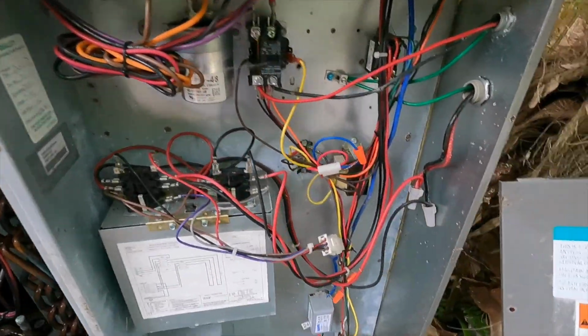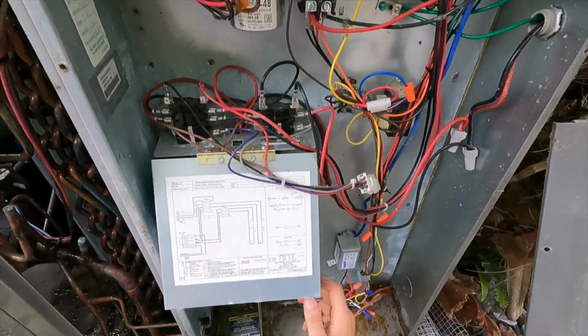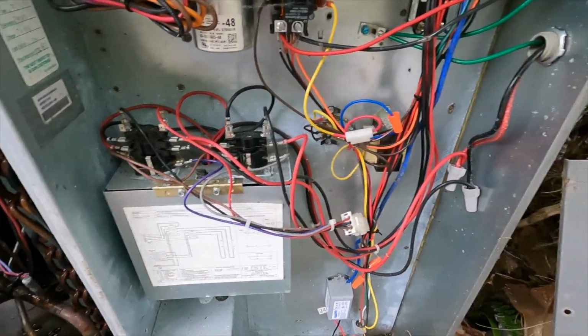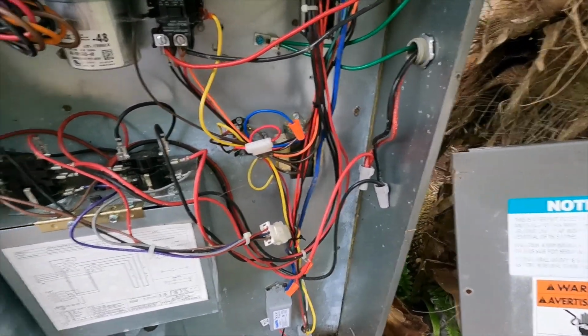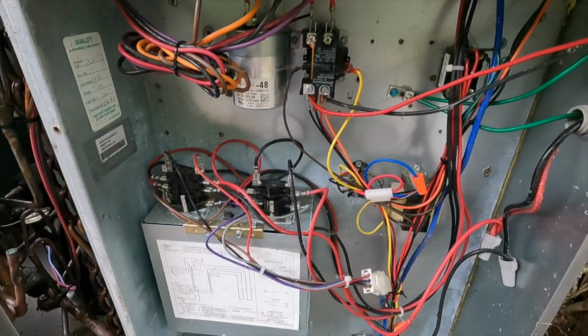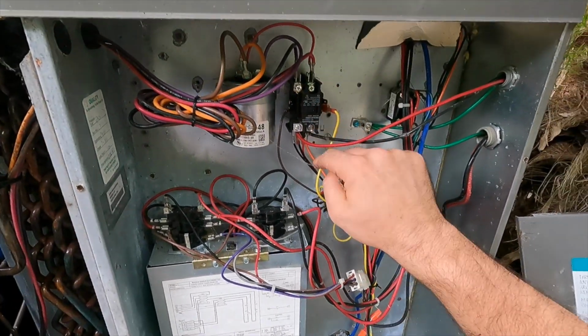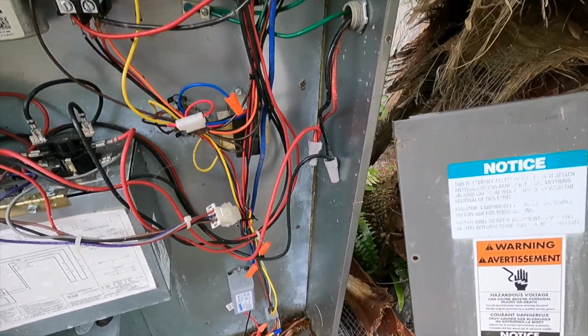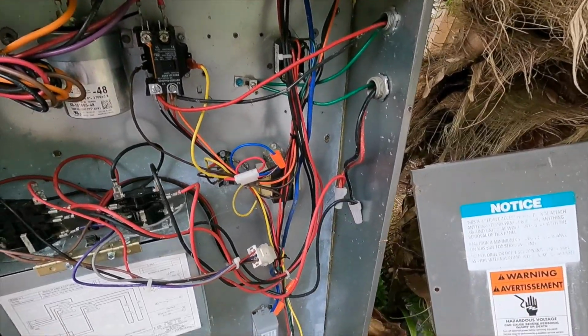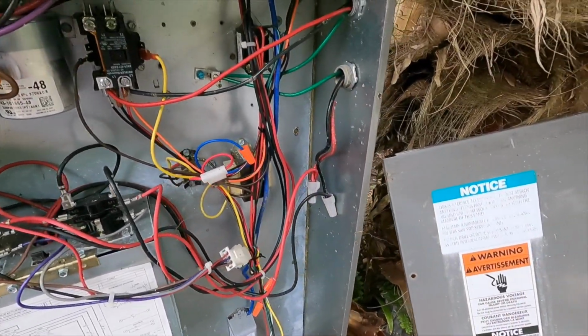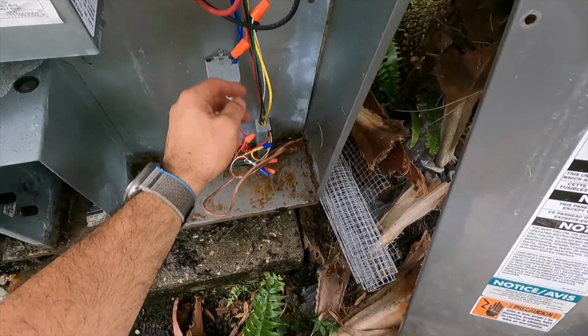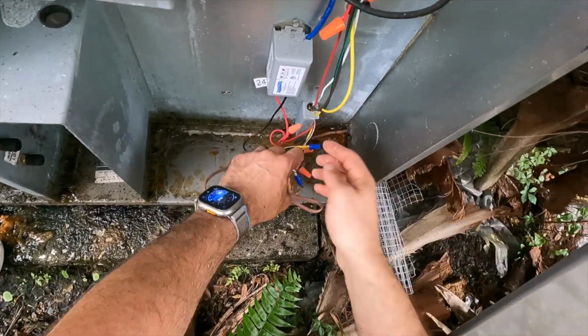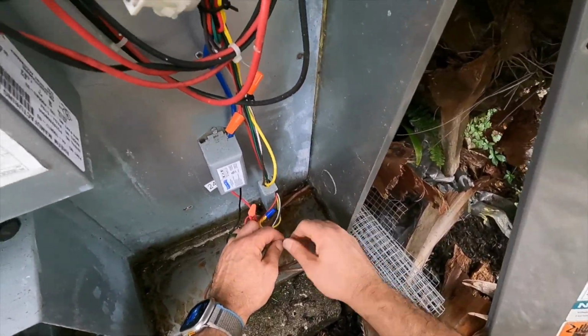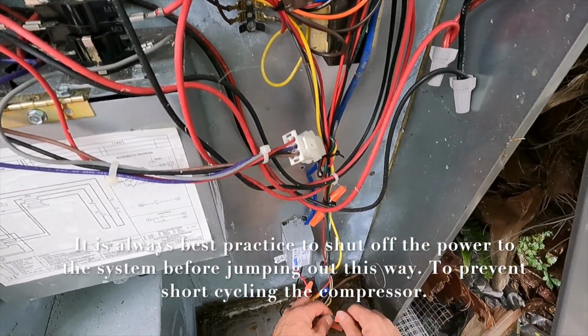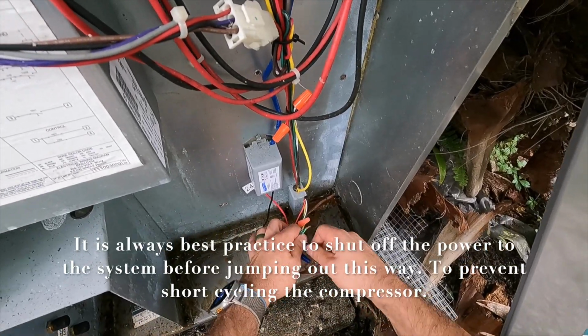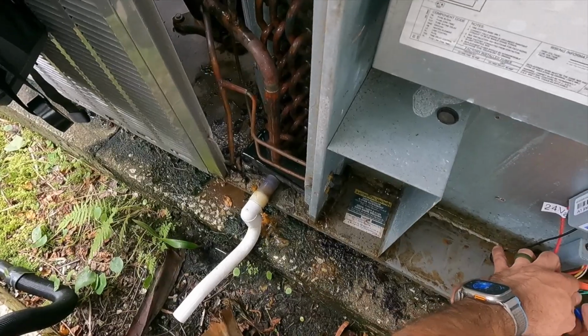So we got our 45+10 capacitor, fuses for our heater, 2 heat sequencers, so at minimum it's a 10 kW, possibly 15 kW. Sweet. Single pole contactor looks good. Transformer looks all right. Wires for our UV and our blower housing and heater. So let's go ahead and jump this thing out and get some measurements going. So we're going to do this by jumping out our cool, our fan, and our power.